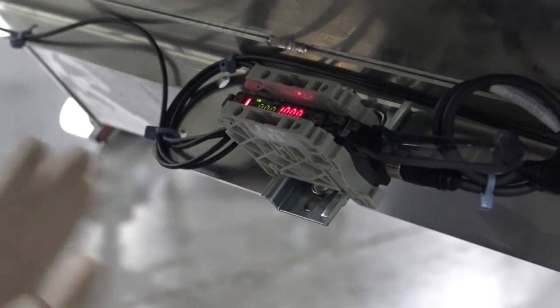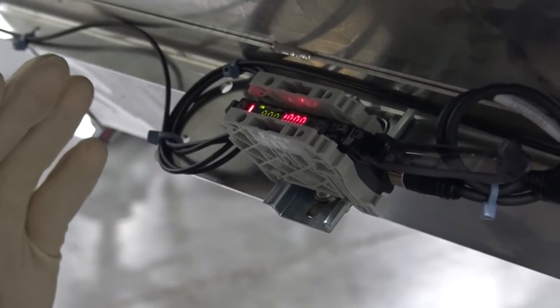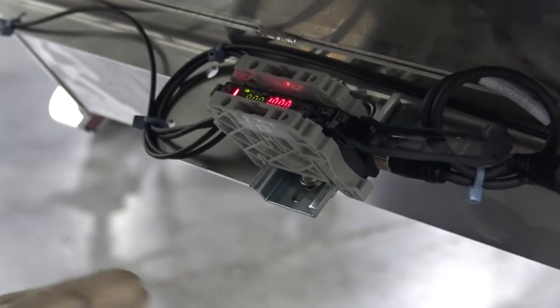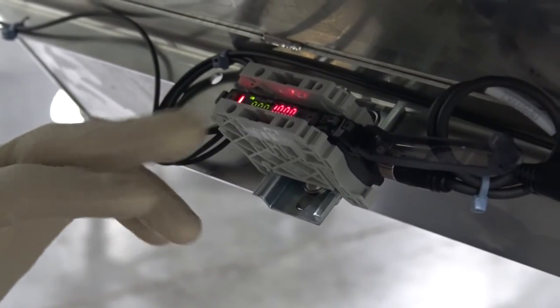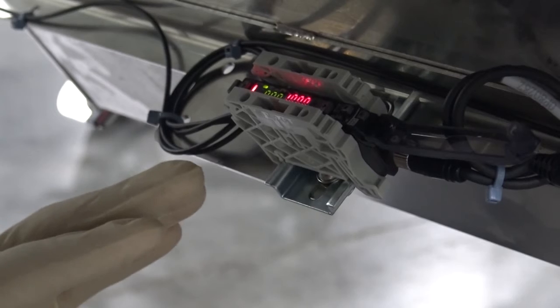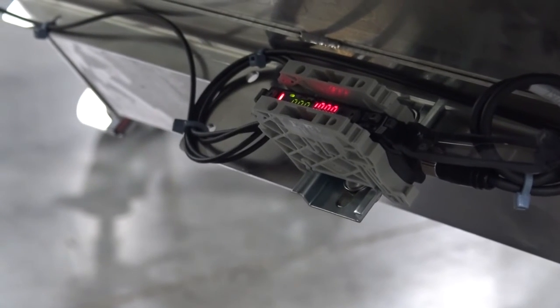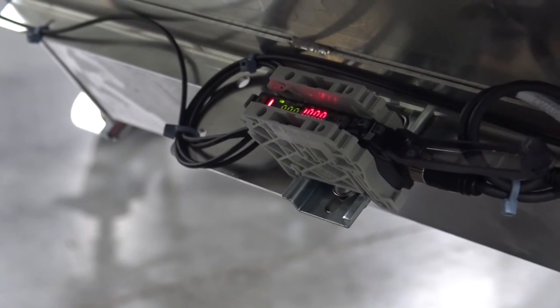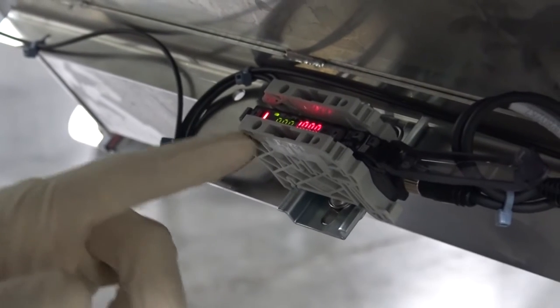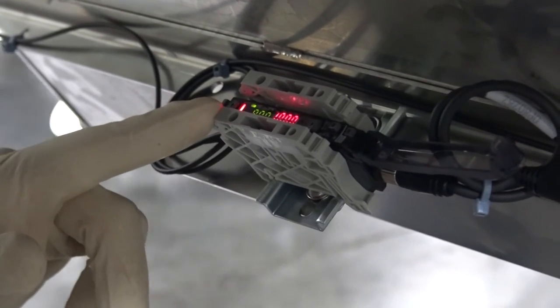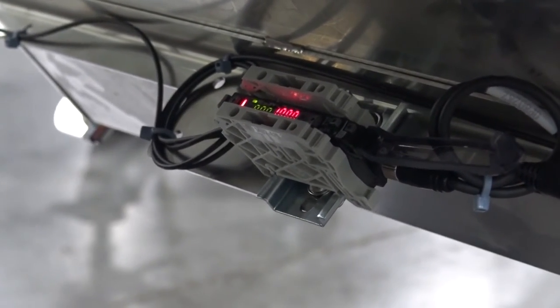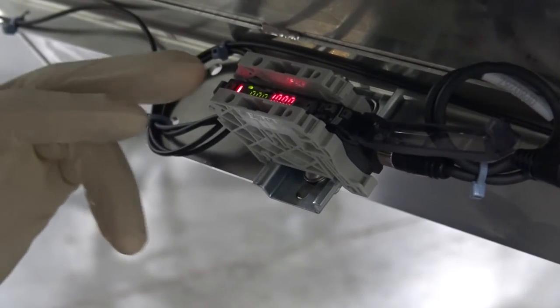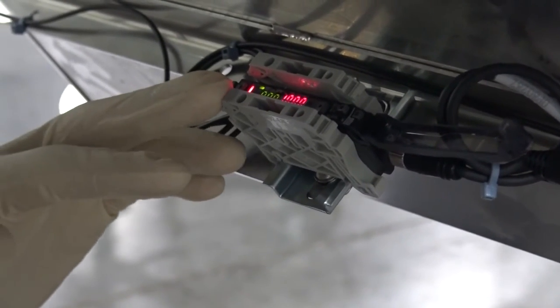Okay, so now we're receiving 100% of light, and at a 20% blockage, we'll send the signal, and you can adjust that according to procedure. If you're rejecting too many bags, you might want to lower that value and trip maybe at 70% or 60 or 65. But if you're not rejecting enough, you might want to raise it up towards 90 or 95%.